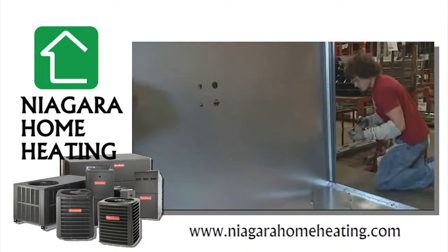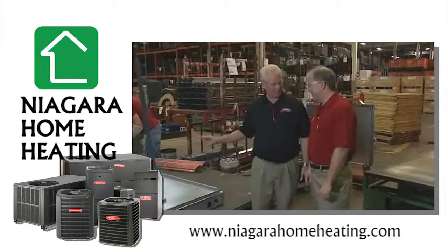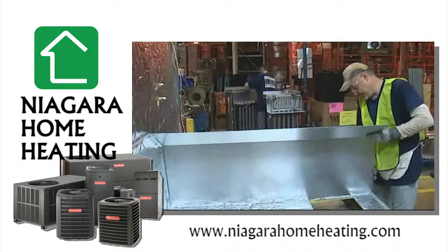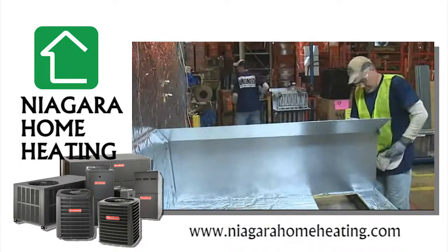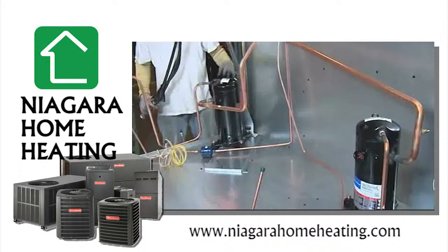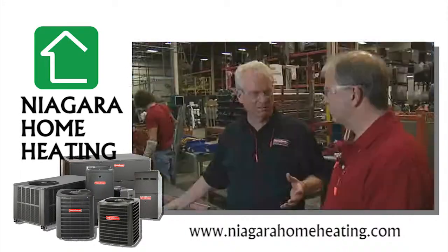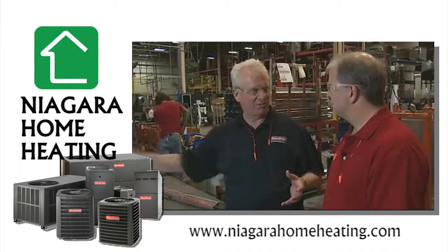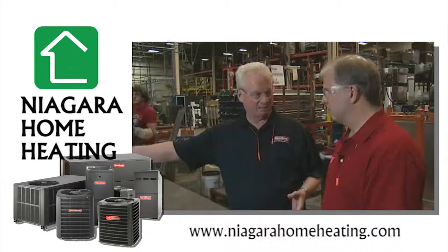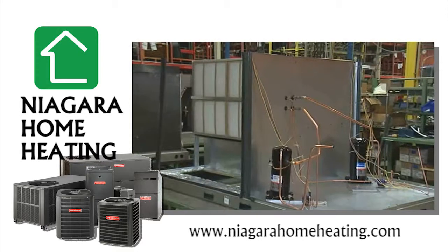This chassis runs 7.5 to 12.5 tons. Again, some of the same concepts and principles that went into the design of the smaller product apply here. Designed the footprint to match existing curbs. All of our 7.5 and higher have 2 refrigerant systems. Customers told us it's very important in a commercial application, if they have anything wrong with a unit, that if they just have one side go down and still have some cooling, they can keep their business running. We listen to our customer, and every design unit 7.5 and up has 2 equal size systems so that it can always be in operation.